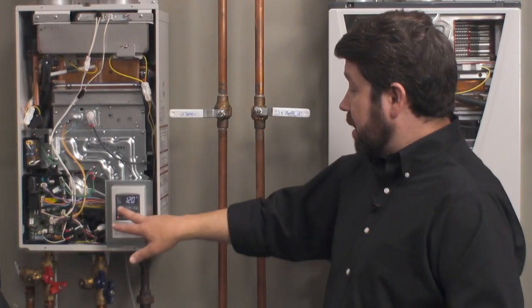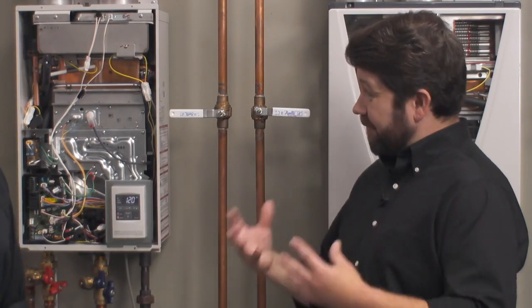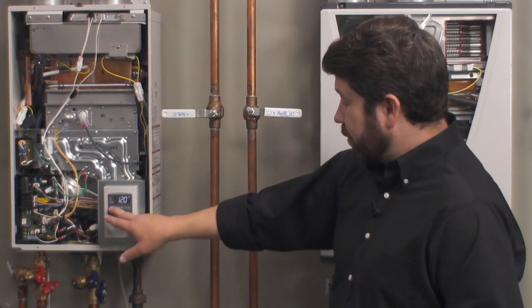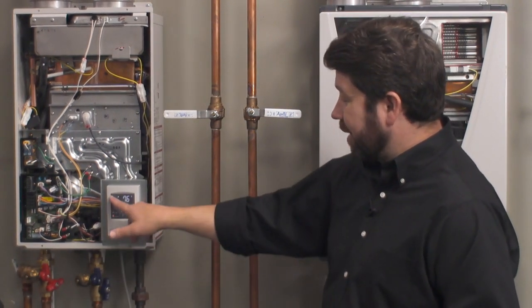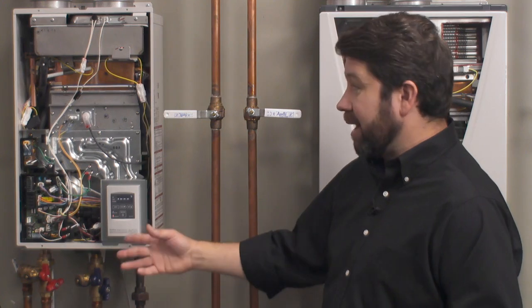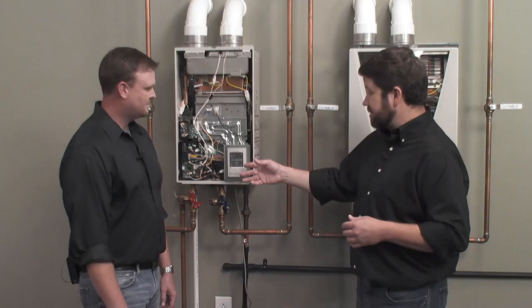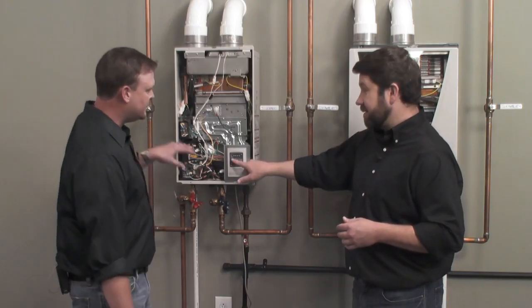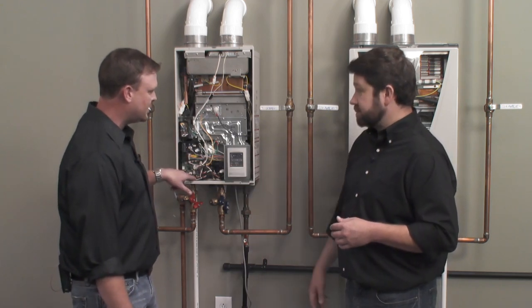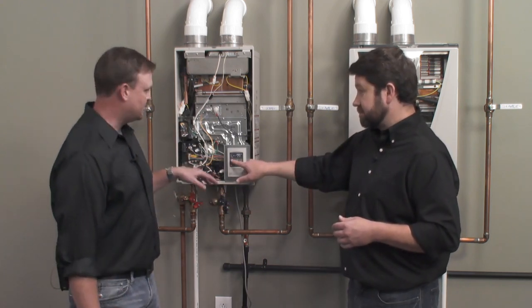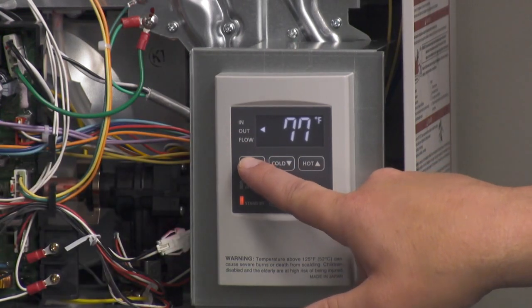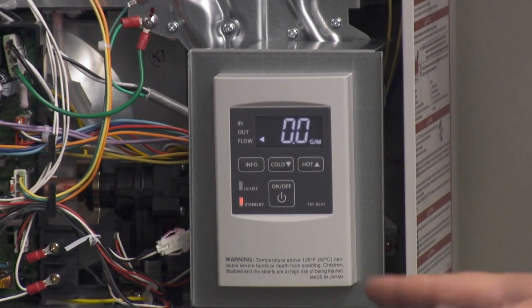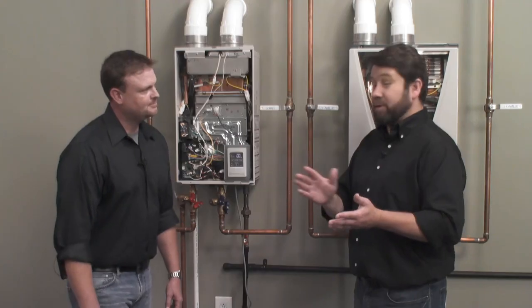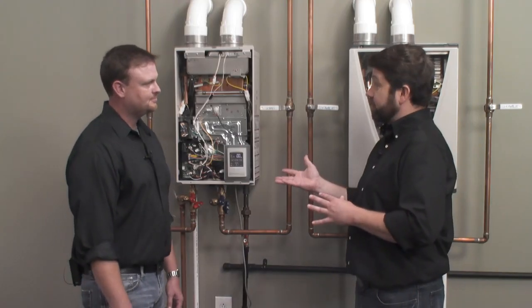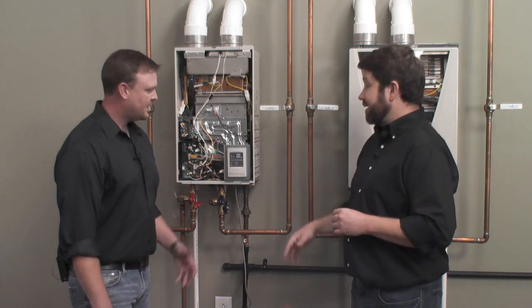Another neat thing, and I really like this, having been a serviceman out there in the field, when we press that info button, I can immediately see what my inlet temperature is. I can see what my outlet temperature is, and it'll take a second to search that. So we're sensing temperature all over this thing. We've got an inlet temperature and an outlet temperature. And actually, we don't have this hooked up to water right this minute, but it is saying it's 77 degrees, and that's our ambient temperature in here. We can also see the flow. So really quickly, I can see what the flow is and what my temperature rise is, and that helps me in certain cases to be able to diagnose. Okay. Now, easy to understand too.